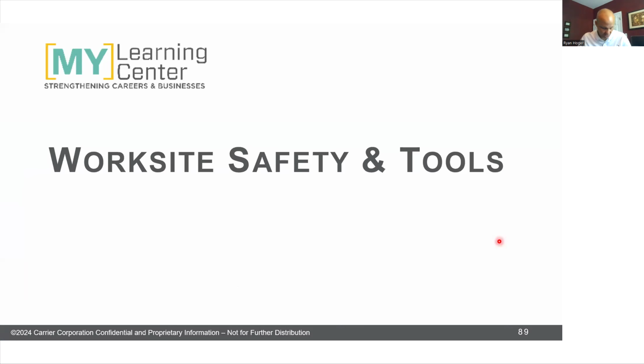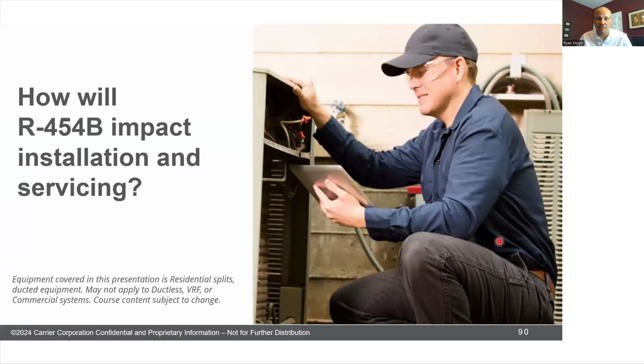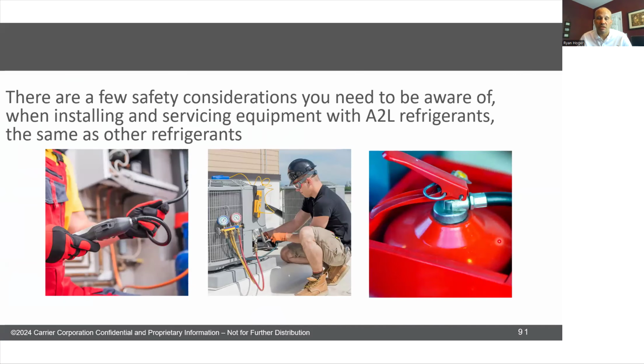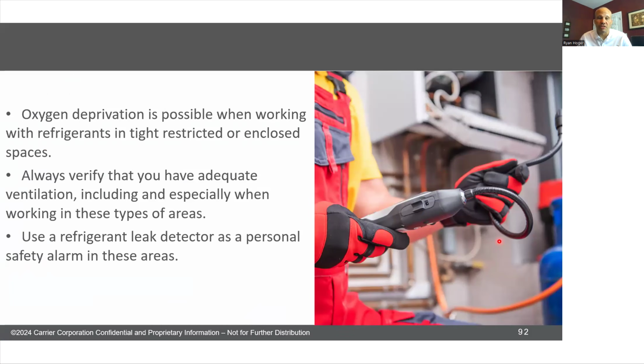From a general safety perspective, let's hit a couple of the general safety things. Refrigerant leak detectors. Obviously, if you have a leak detector that detects R-22 or 410A and it does not detect 454B or R-32, that's not super helpful then. You just need to make sure whatever leak detector you have can detect the thing you want to find. That's like a no-brainer sounding thing, but just check the specs of whatever one you own. See if it will, in fact, detect the new refrigerants, and if not, then you're shopping for a new one.